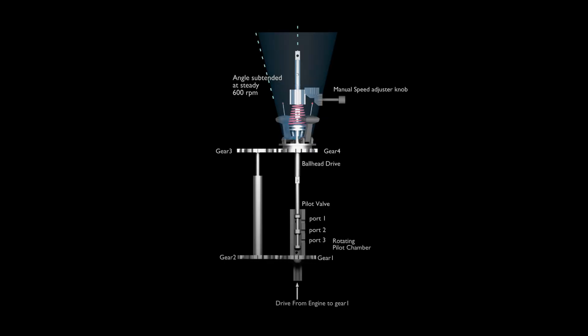This lag originates from inertia of the engine against rotational acceleration or deceleration. Engine, with all of its rotational mass, will need time to change speed whenever there is a change of fuel admission. So an increase in fuel, when port 2 is uncovered, will not instantaneously bring up engine RPM. Engine needs time to accelerate to reach the desired RPM. During this time lapse, port 2 remains open and fuel setting will continue to increase.